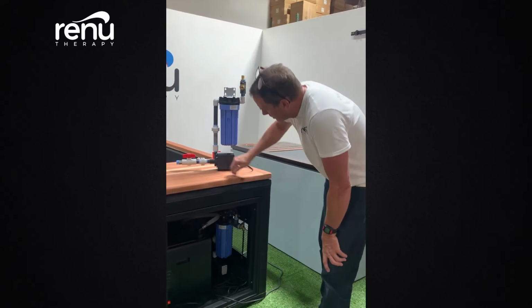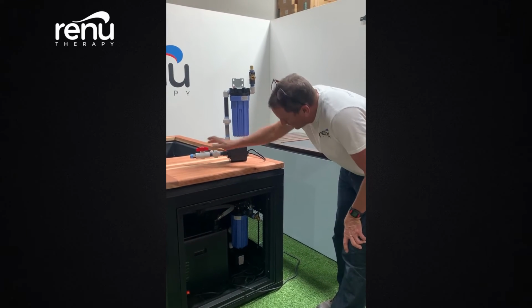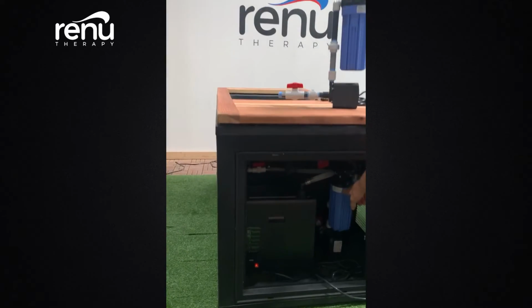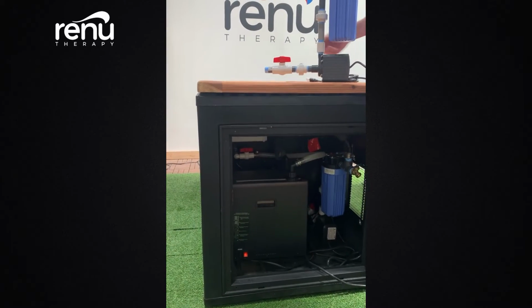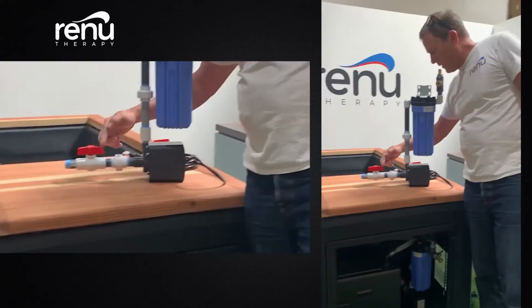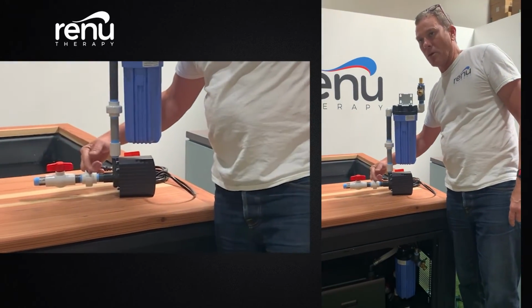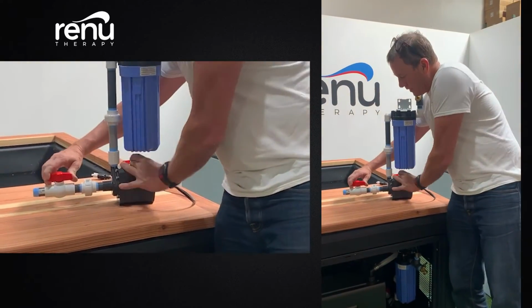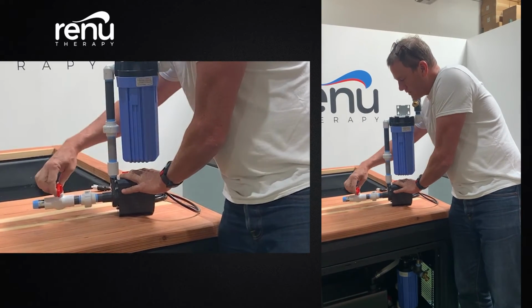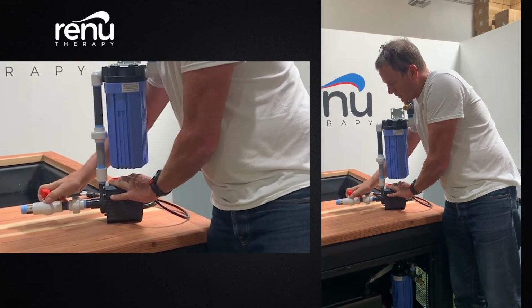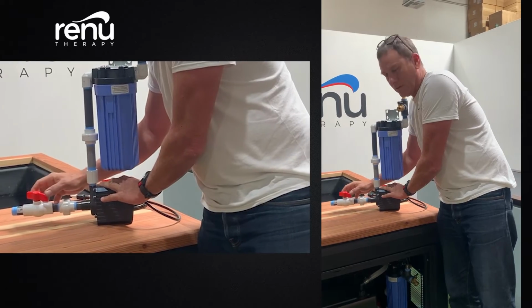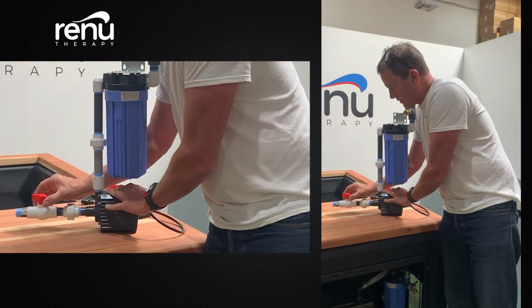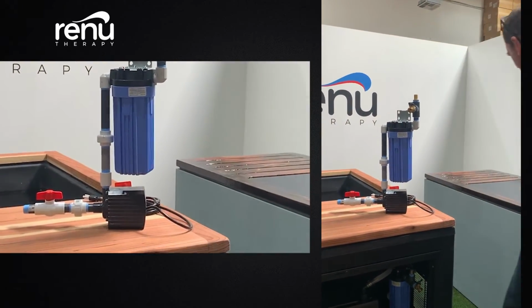The other thing with low water flow is you want to make sure that these valves are in the open position. There's one up there and one down there. If the handle is flowing the same direction as the pipe, it's open. If it's the other way, it's closed. Sometimes they'll be slightly closed or not all the way open. That will definitely slow your water flow down. So you just want to make sure those are open.